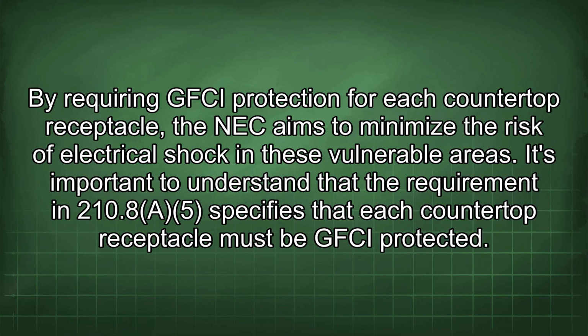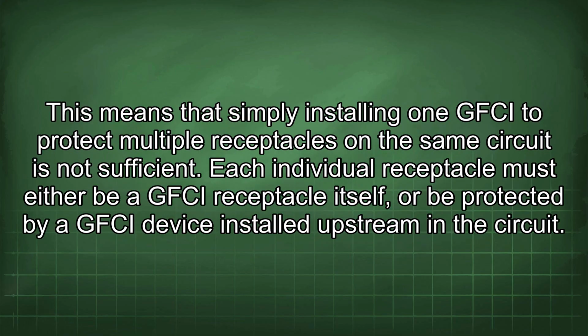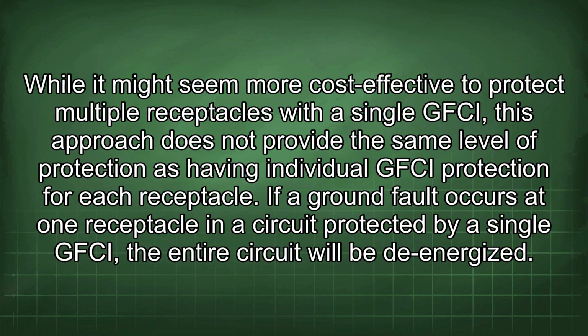It's important to understand that the requirement in 210.8(A)(5) specifies that each countertop receptacle must be GFCI protected. This means that simply installing one GFCI to protect multiple receptacles on the same circuit is not sufficient. Each individual receptacle must either be a GFCI receptacle itself, or be protected by a GFCI device installed upstream in the circuit. While it might seem more cost-effective to protect multiple receptacles with a single GFCI, this approach does not provide the same level of protection as having individual GFCI protection for each receptacle.